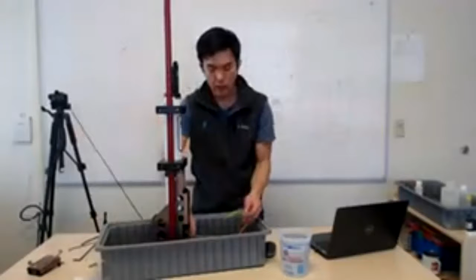So I filled my syringe with deionized water. I'm going to take this yellow tubing, insert it there, hold it in place, and then just push it through. I can see DI water leaking out from beneath the sensor. That's good. That means any water around the pH sensor is now clean, deionized water. I'm just going to do that one more time. I'd recommend doing it at least twice. It's an easy process.